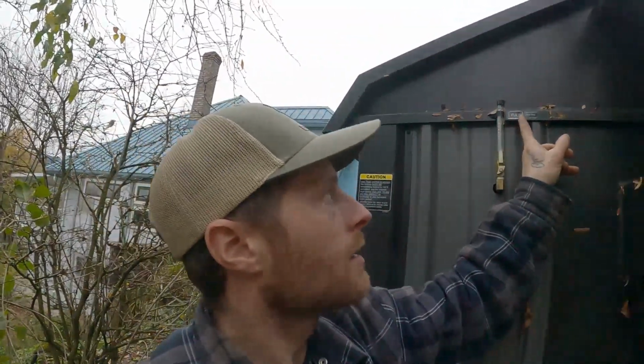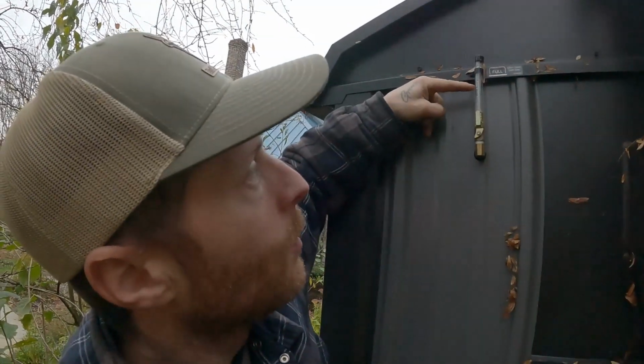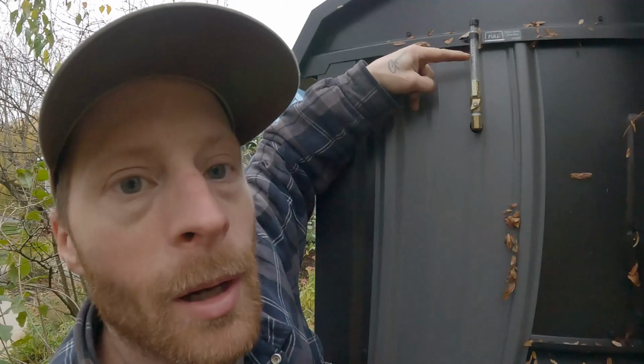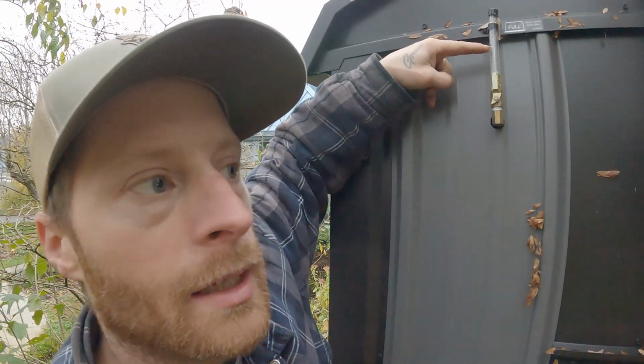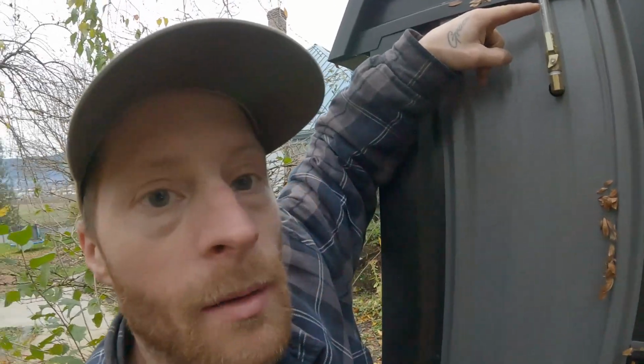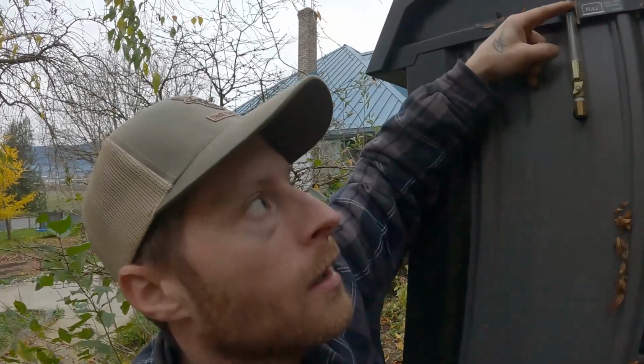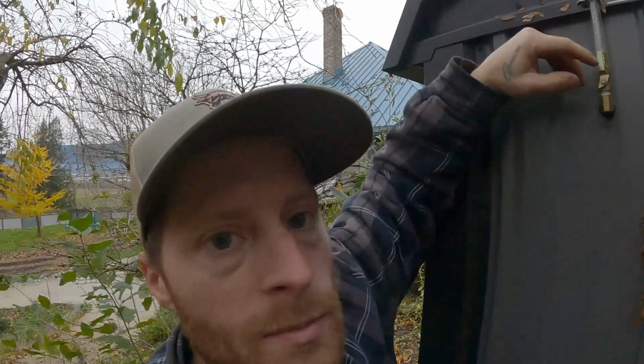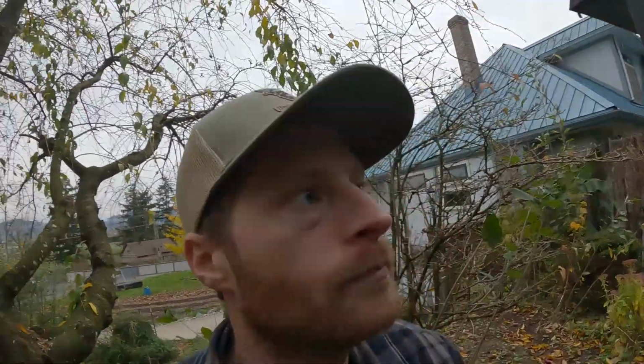Here's what I'm looking for — this is my sight gauge to let me know how much coolant, water, and corrosion inhibitor we have in here. The full mark's up here, so we don't want more than about up to there before we get it started. Once it's up to operating temperature, 185 degrees Fahrenheit, we'll check it again to make sure it's full. But if we filled it more than that, it would spew out everywhere, since this is an open loop system — open to the atmosphere, no pressure in it, not a sealed unit.